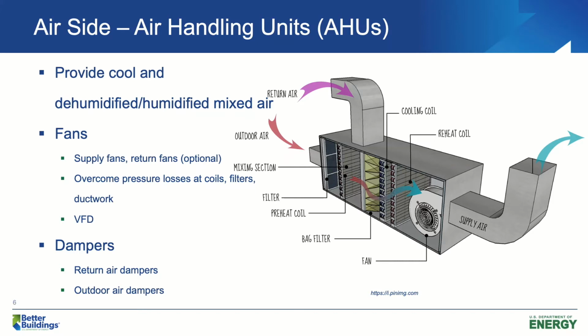We also have dampers, return air dampers and outdoor air dampers. The job of these dampers is to make sure that we get the right amount of outdoor air for ventilation purposes. You probably want to check the operation of the outdoor air dampers regularly. Make sure that they are not stuck open or stuck closed. If they are stuck closed all the time, you thought you got needed outdoor air, but you didn't. If outdoor air dampers are stuck open all the time, you thought you were modulating the outdoor air dampers to match whatever the demand is, but in reality, you got a lot more outdoor air than needed.